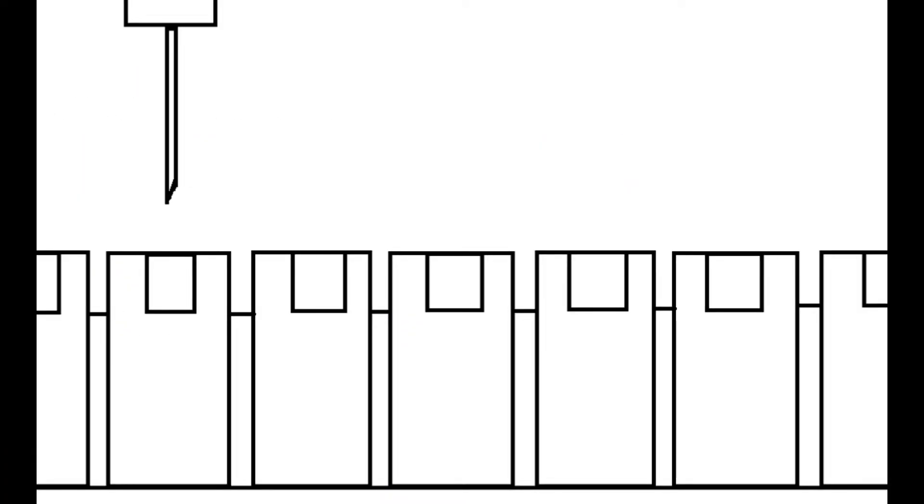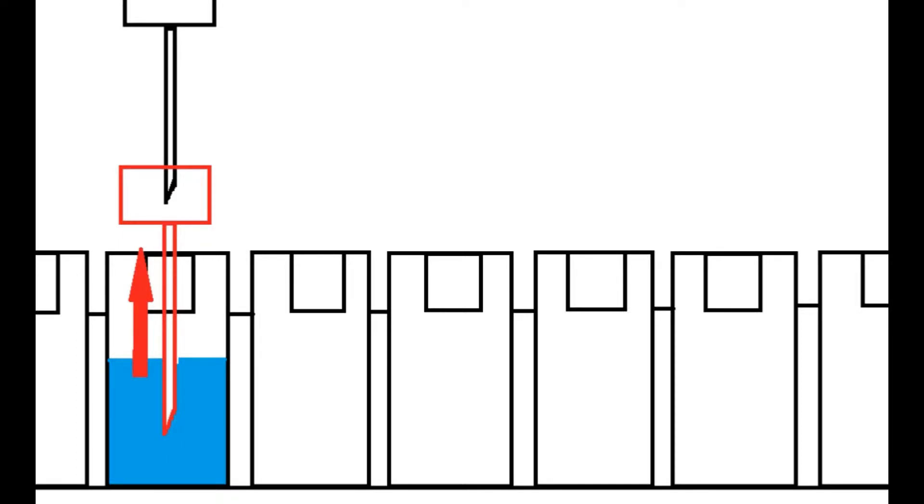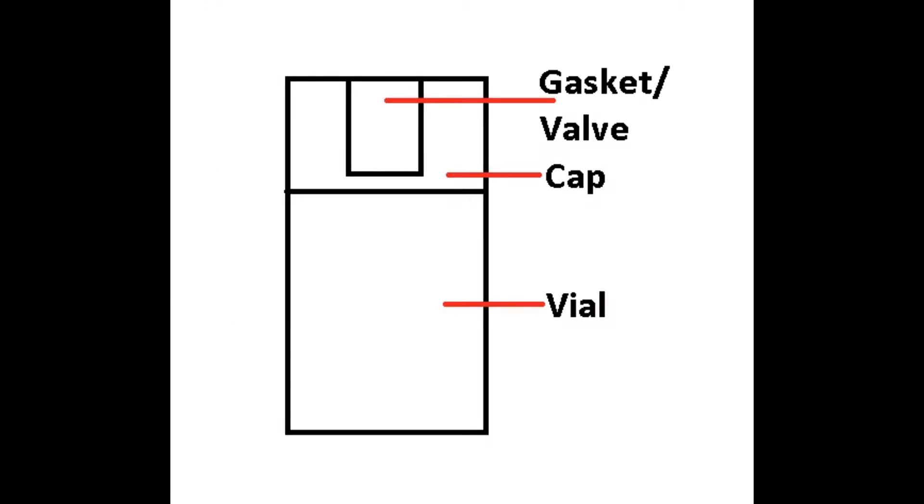Those samples prepared earlier are now accessed. A tiny needle pierces an HPLC vial and draws out a fractional amount of the sample. This is called the injection volume. One vial can facilitate an easy 100 runs if 10 microliter injections are used. But the amount can vary, and this depends on a large number of factors.